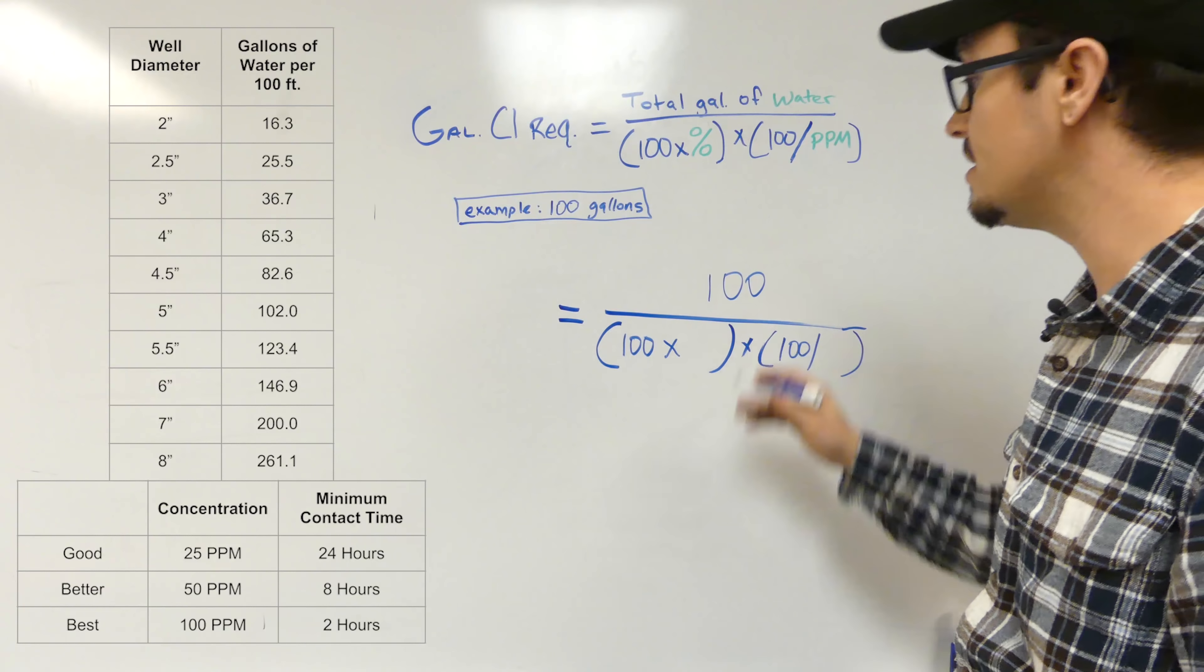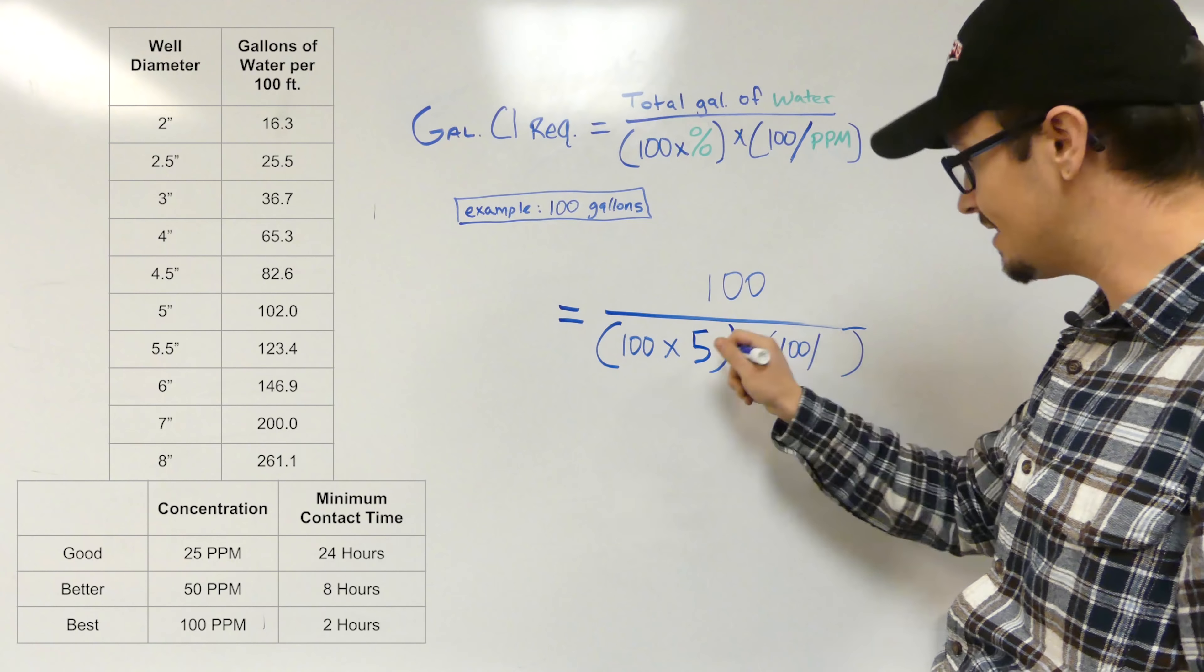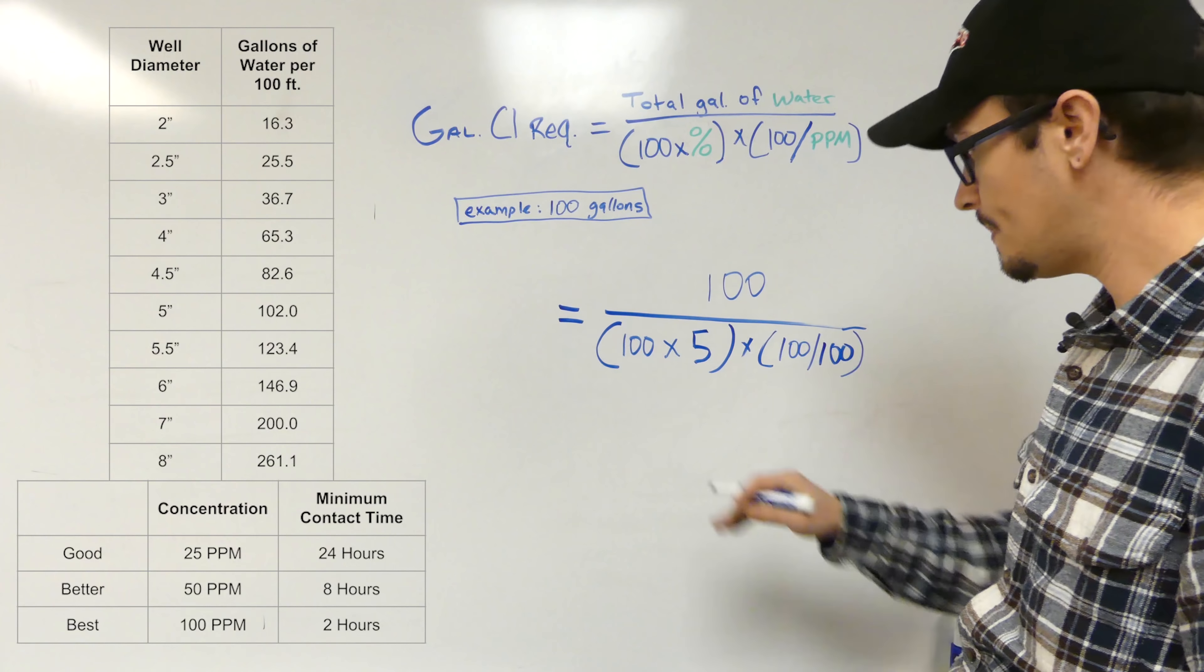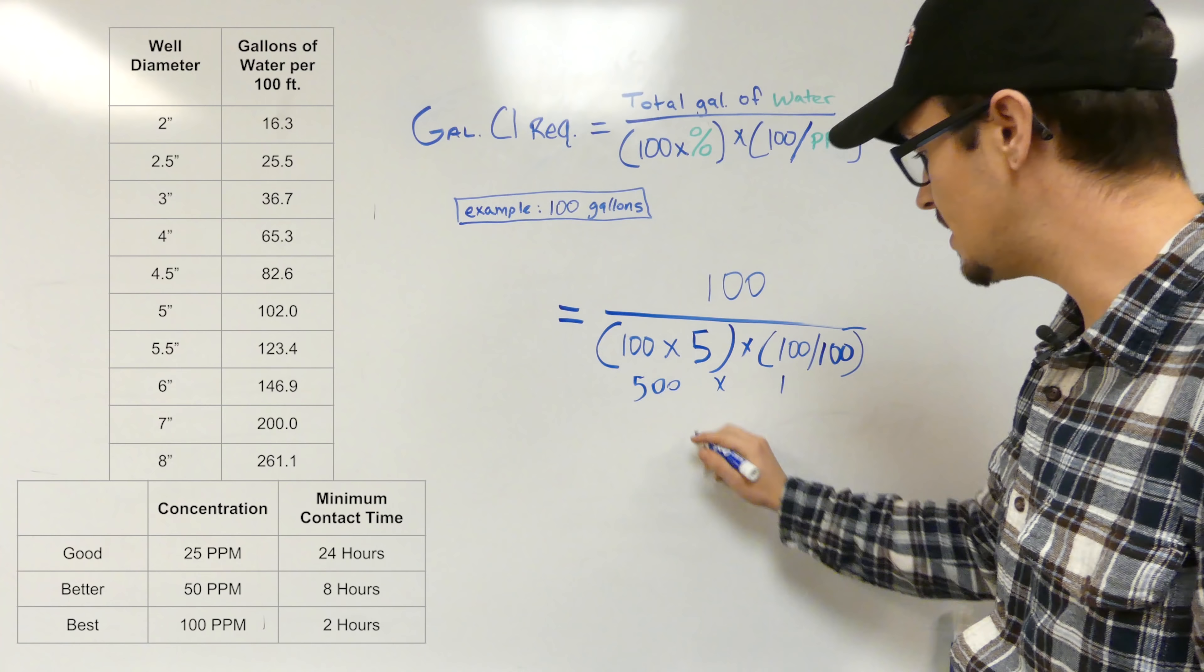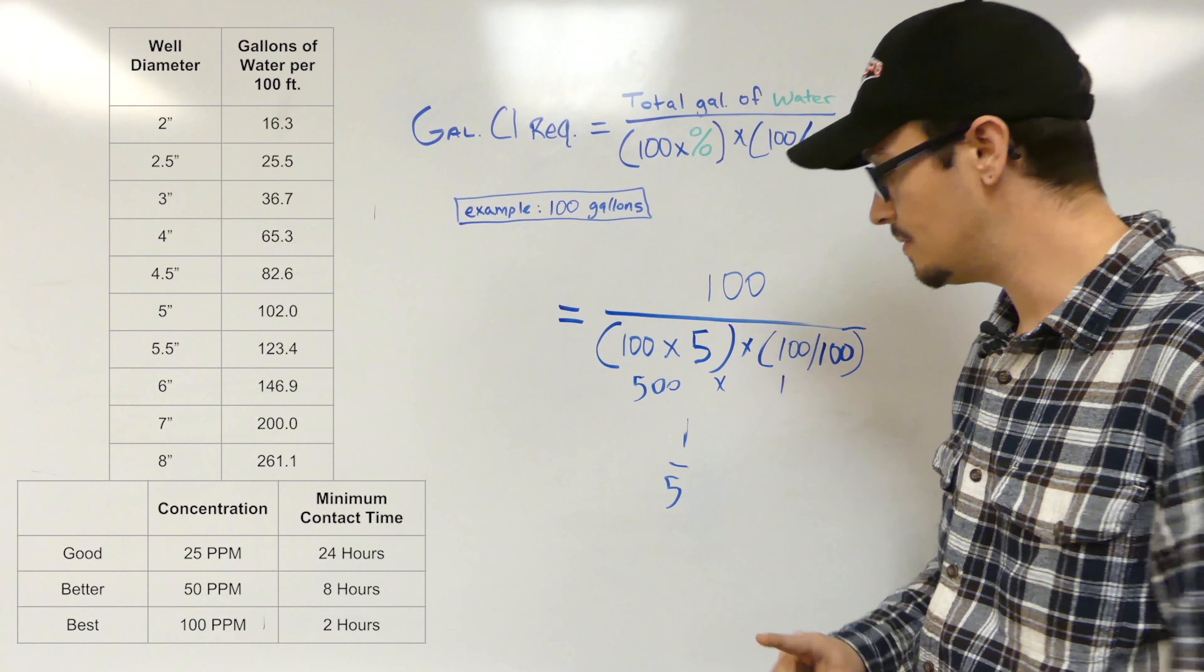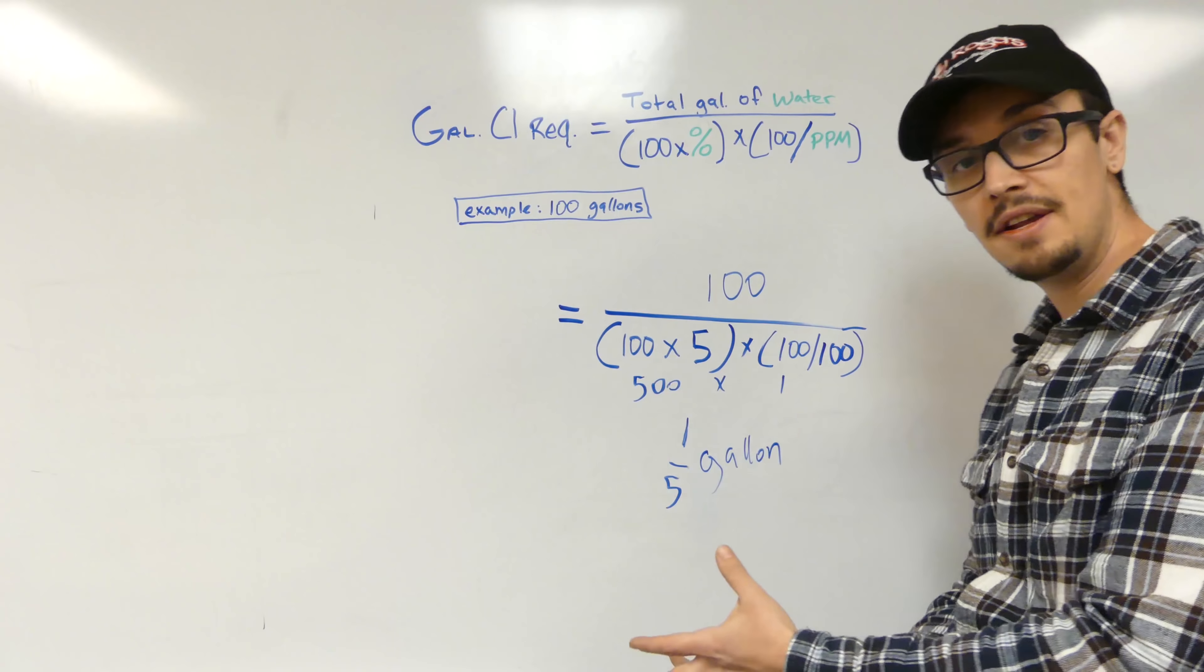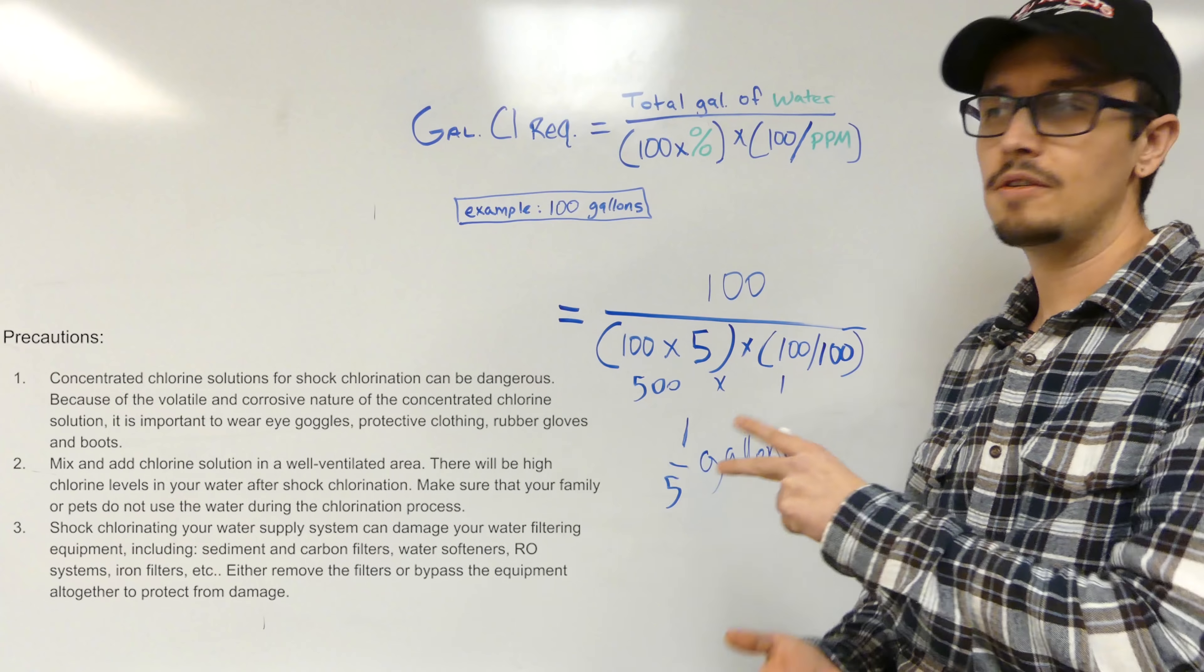We've got total gallons of water. We're going to put 100 up here. That's how many gallons of water we're trying to treat. Then we need to do our percentage. We're just going to use off the shelf store-bought bleach that is 5%. Just remember, 5% is 5 in this particular spot. I mentioned 100 parts per million is usually what you want to shoot for for a lower retention time as well as a higher effectiveness because of the concentration. So we're going to do 100 here. Let's boil this down. We got 500 times 1. Basically we've got 100 over 500, which we can reduce down to one-fifth of a gallon of 5% store-bought bleach to super chlorinate at 100 parts per million. A really shorthand way of calculating that. Hopefully this helps you determine exactly how much chlorine to put in.